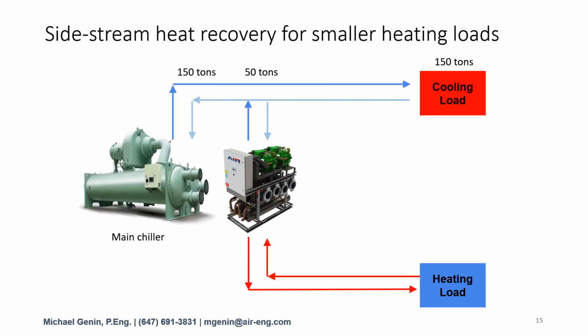Here's a slight modification and a more realistic scenario. The cooling load is consistently larger than the heating load, or perhaps we've chosen to only tackle a small portion of the heating load. We have 150 tons of cooling in total that we've chosen to install, but we've only taken a 50-ton heat recovery chiller in this case.